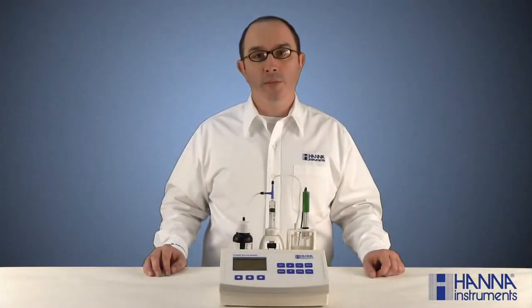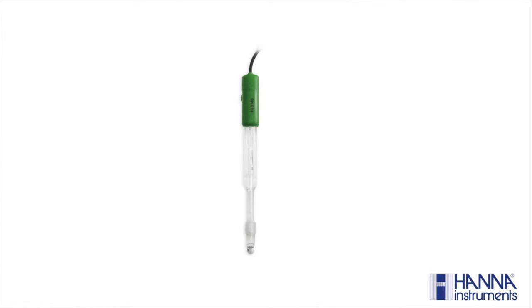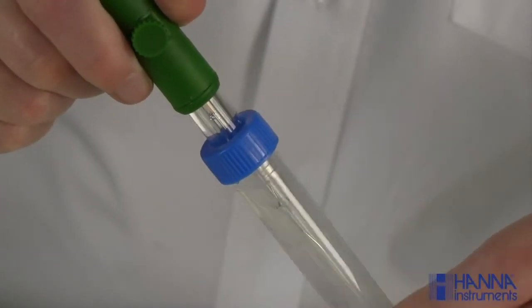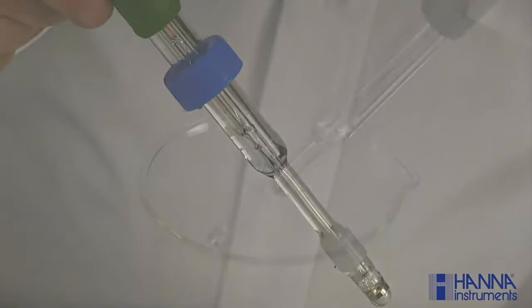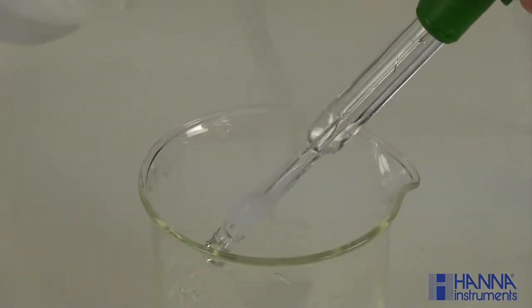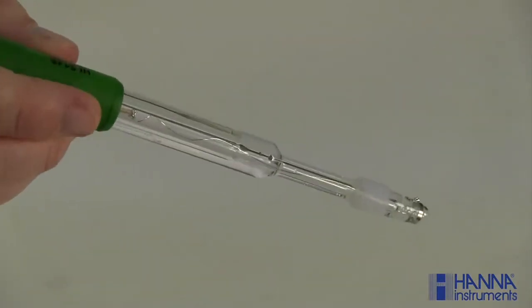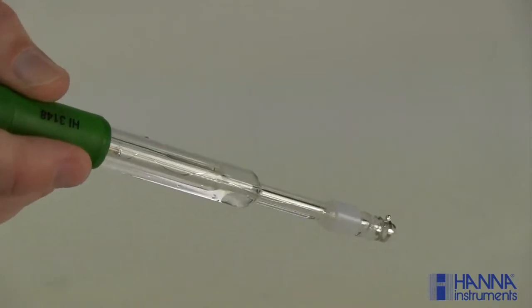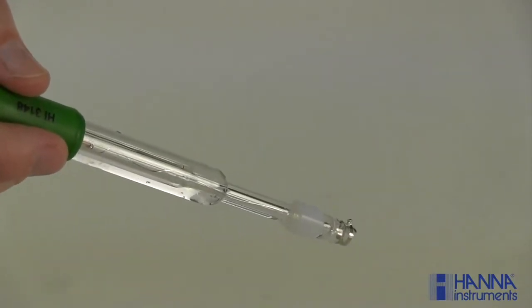Before we begin our pump calibration, we'll need to prepare our electrode. The HI-84500 mini titrator comes with the HI-3148 ORP electrode. Simply remove the protective cap. Don't be alarmed if you see any salt deposits. This is normal. Simply rinse the electrode with DI water. Inspect the bulb for any air bubbles formed during transport. The electrode will not function properly if they're present.